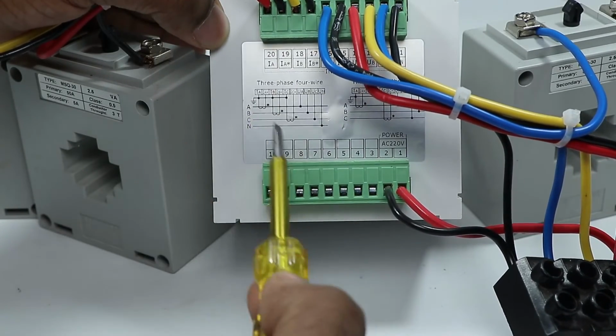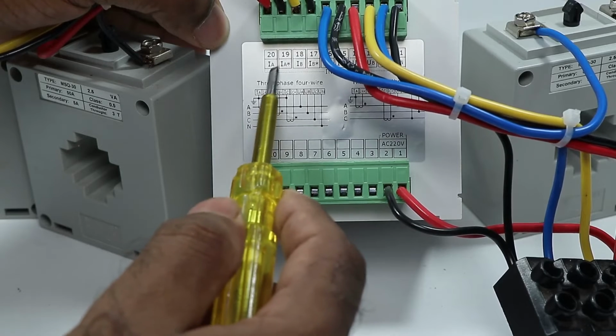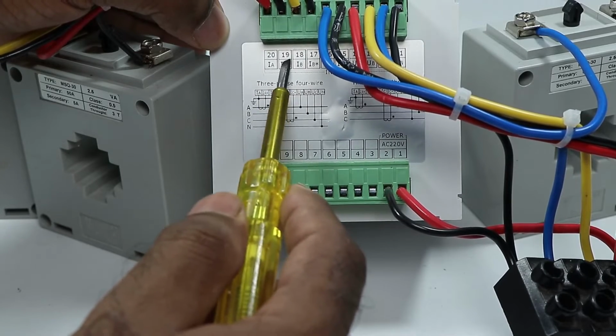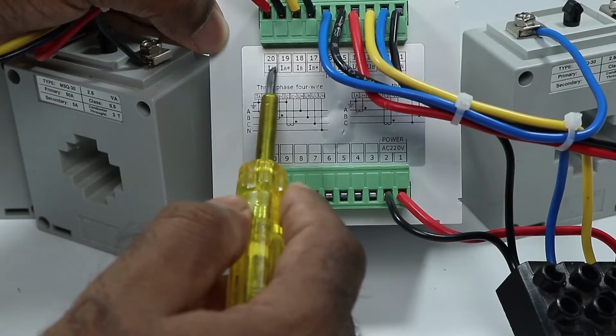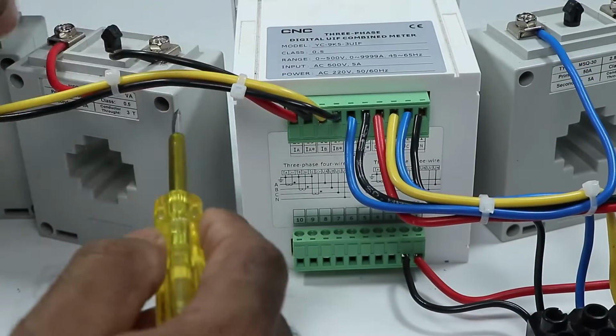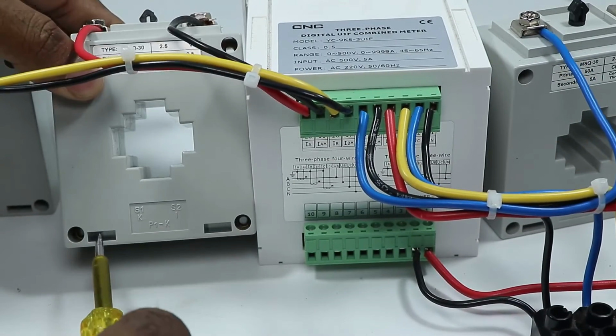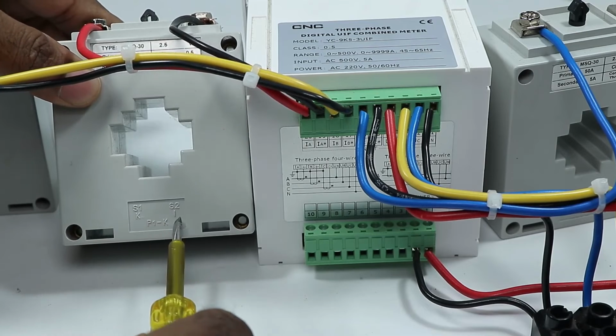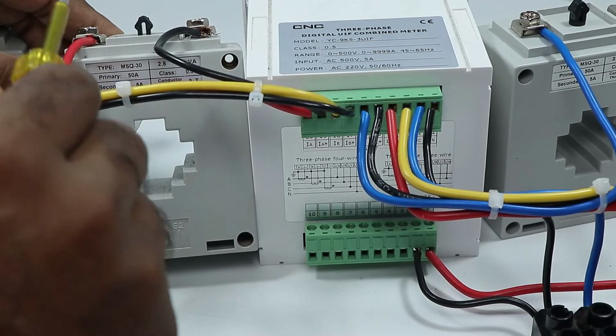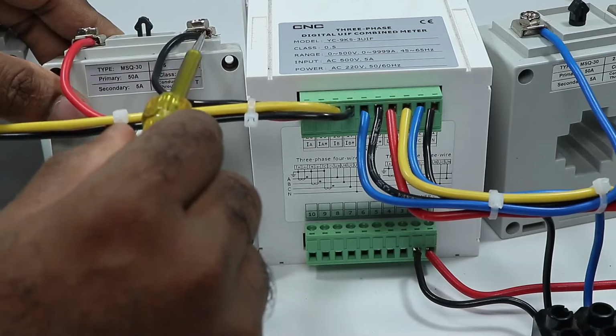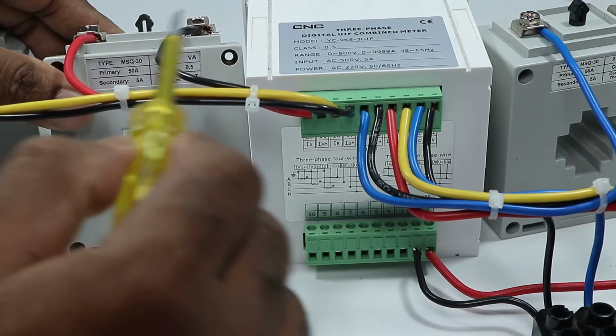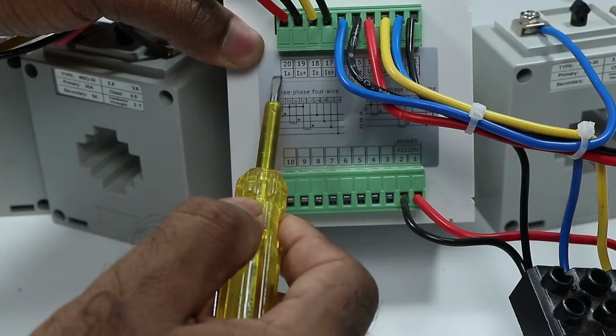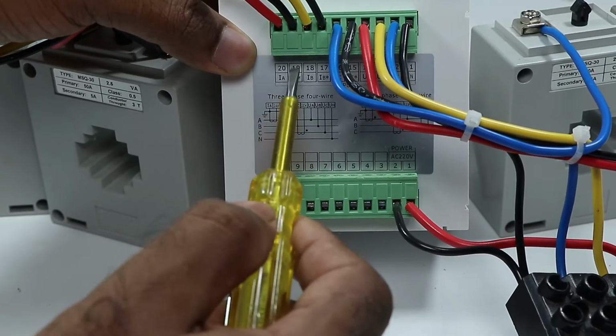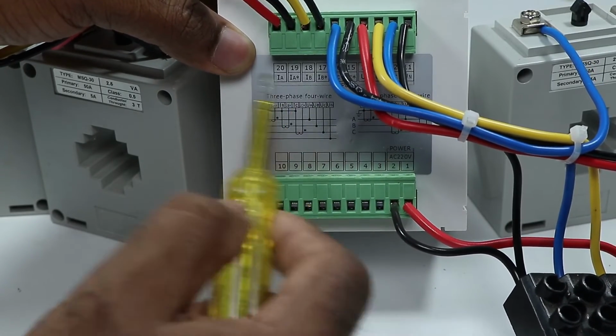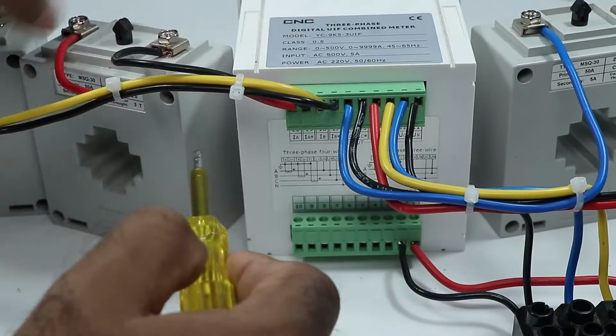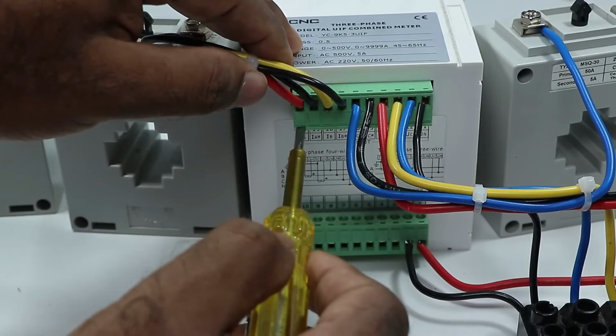Don't go by terminal number. Here IA is written, and here IA star is written. The terminal at which IA is written connects from the S1 terminal of the CT, here marked S1 and S2. S1 is on this side. So the power supply from S1 terminal will be supplied to the IA terminal, and at IA star you connect the wire from the S2 terminal. So I connected these two wires at these two terminals.